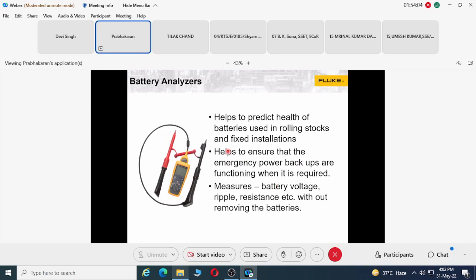Because of this, the battery measurement is actually very, very important, and it helps to predict the health of batteries. When you have an array or bench of batteries for a purpose, maybe 10 or 15 numbers of batteries in an array, if one fails, the entire other batteries can also get defected in no time. That's why you need periodic testing to ensure you are not spoiling the entire bunch of batteries.